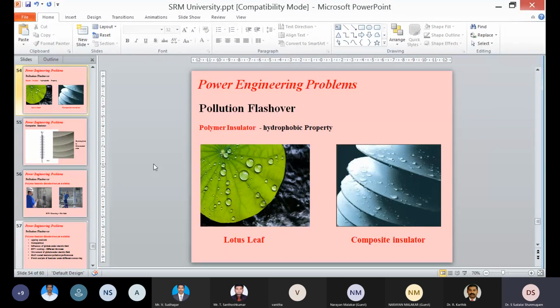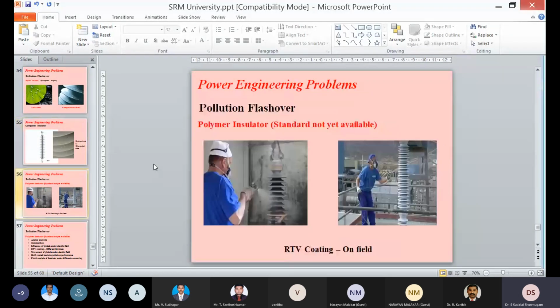And traditional insulators, that is ceramic insulators and glass insulators, all have a hydrophilic surface property. So we are addressing it in two ways right now. One is, wherever more problems are happening, we are moving to RTV coating, room temperature vulcanized coating. On the surface of the insulator, we coat polymeric material to enhance its pollution withstand severity.